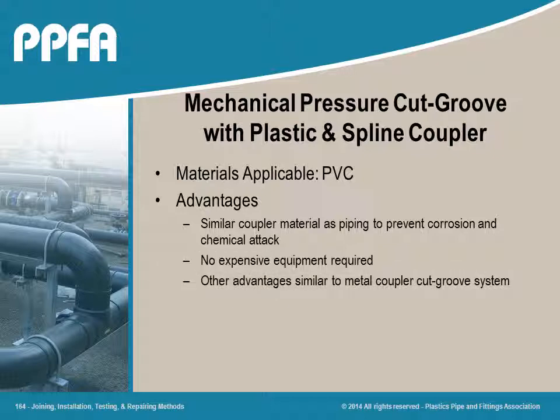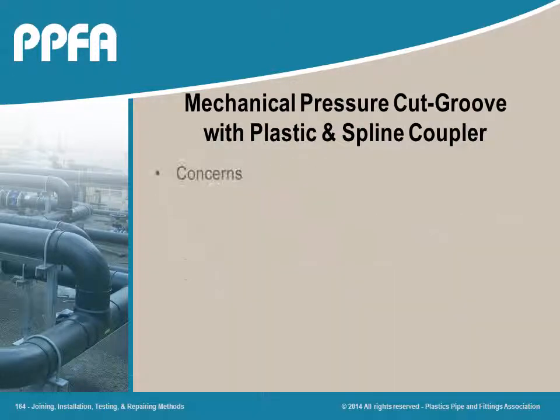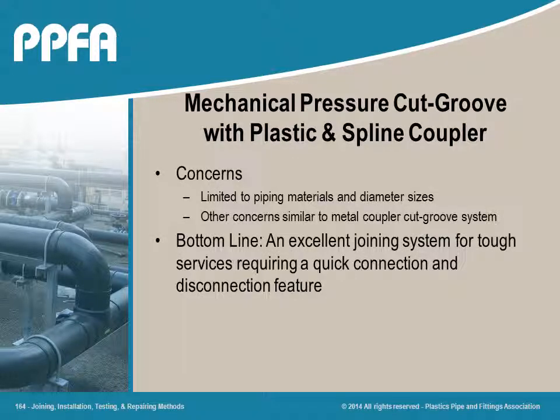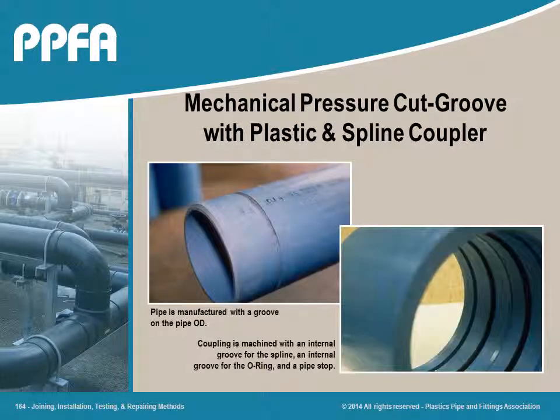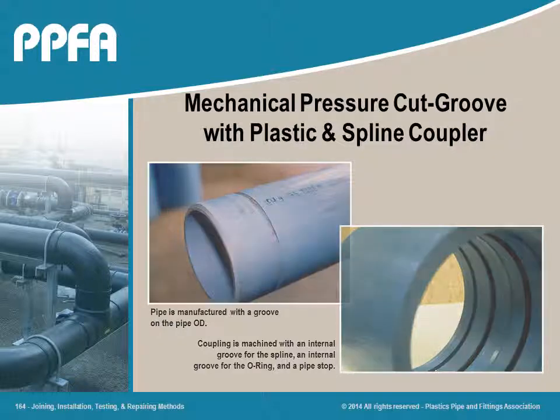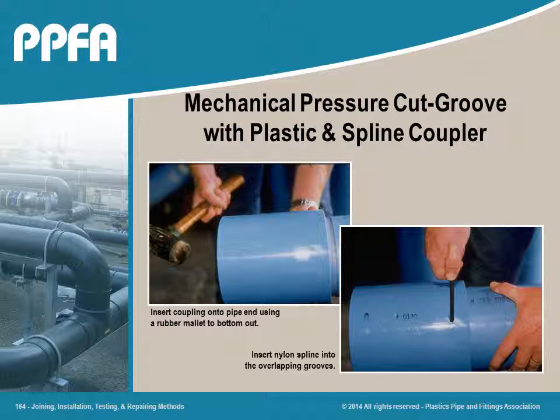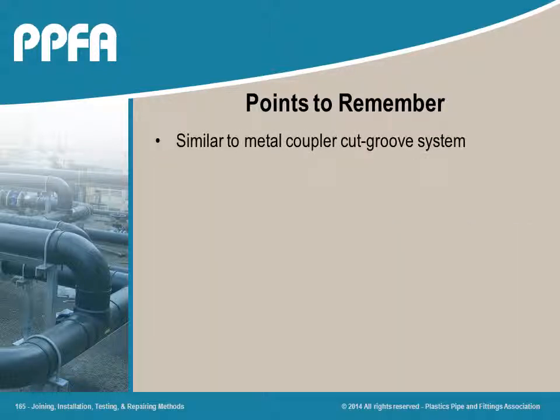This mechanical joining system is similar to the cut and rolled groove system mentioned before. However, instead of a metal coupler, a plastic coupler with plastic splines is used. To date, only PVC piping is used for this joining method. The two advantages of this system are the removal of any metal coming in contact with the fluid being handled, and the lack of any expensive joining tools. There are presently two manufacturers who provide this type of joining system. Make certain that elastomeric seals are compatible to the fluid being handled. This joining system is mostly used for 12-inch diameter and below.